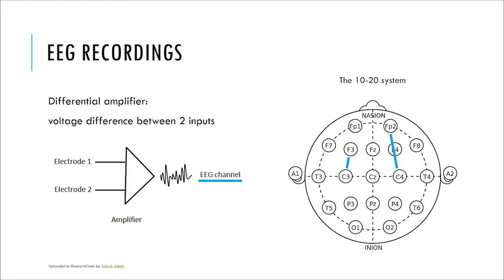To further consider why the montage has an effect on spatial resolution, we have to consider that EEG is recorded with a differential amplifier — the EEG machine records the voltage difference between two inputs, which are the electrodes placed on the patient's scalp. You have electrode one and electrode two, both giving input into an amplifier, and you get one EEG channel out of this. Electrodes are placed using the 10-20 system, which stretches with a person's head so that all electrodes are equidistant in a 10-20 design.